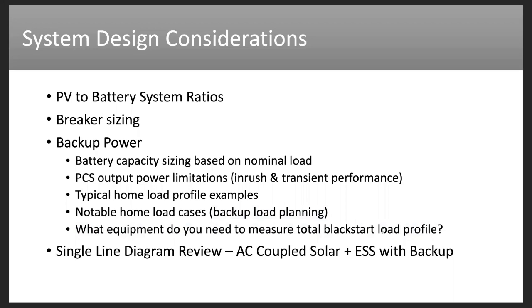Most importantly, when in backup mode, because you want to make sure that you don't overload the battery system, especially when there's no PV. Overnight, your loads need to be served by the battery, and then obviously last through the night till the sun comes up the next morning and the PV kicks back on. And so you want to make sure that there's seamless performance, and you don't overload the battery and cause any nuisance trips during a grid outage. Then we'll also look at a single line diagram review for AC coupled solar plus storage.